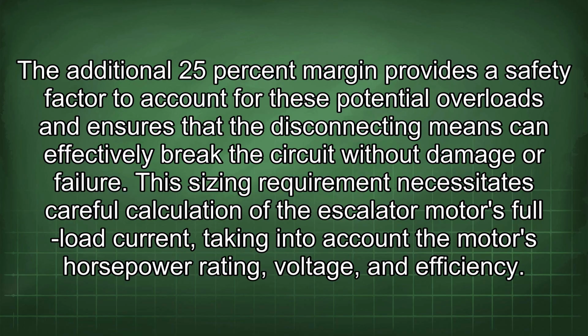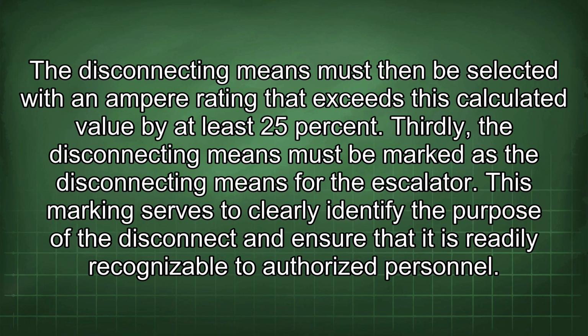This sizing requirement necessitates careful calculation of the escalator motor's full load current, taking into account the motor's horsepower rating, voltage, and efficiency. The disconnecting means must then be selected with an ampere rating that exceeds this calculated value by at least 25%. Thirdly, the disconnecting means must be marked as the disconnecting means for the escalator.